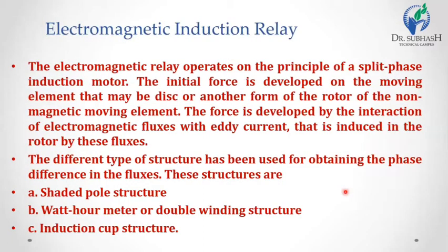Now the electromagnetic induction type relay, which you have seen mounted in old substations. It operates on the principle of a split phase induction motor, where initial force is developed on the moving element, maybe a disc or a rotor, which is a non-magnetic moving element. The force is developed by the interaction of electromagnetic flux with the eddy current that is induced in the rotor by this flux.